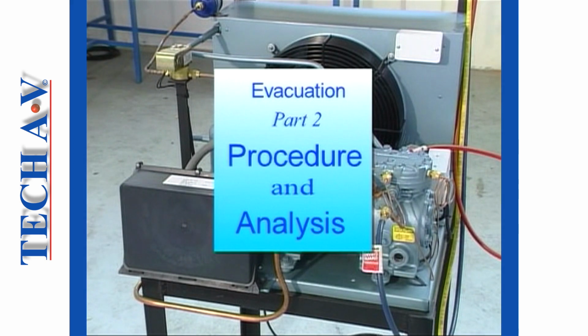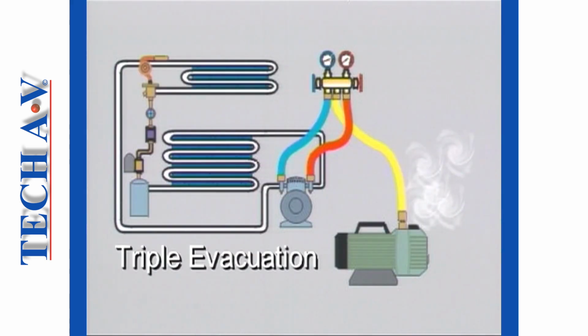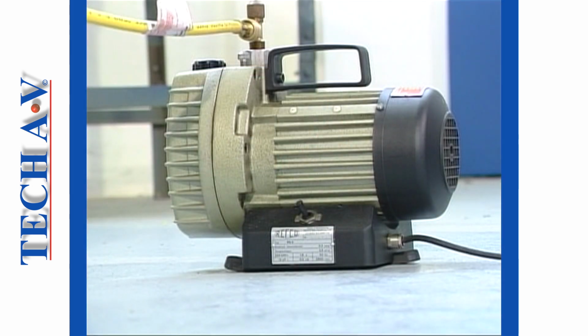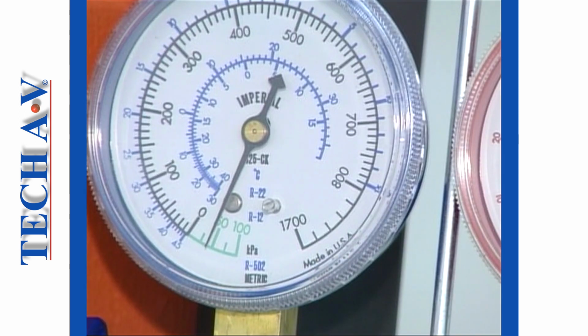Welcome back as we conclude this module with a typical evacuation and analysis procedure. Evacuation of air and moisture from a system is most effectively performed using the procedure known as triple evacuation. The process involves using the vacuum pump to pull a vacuum 3 times.